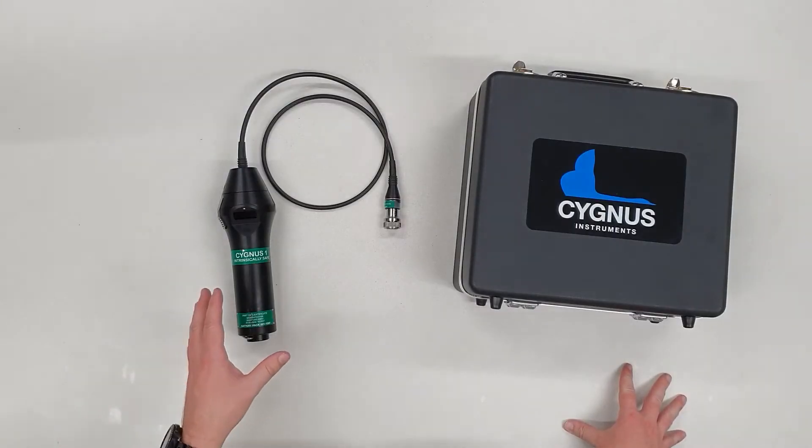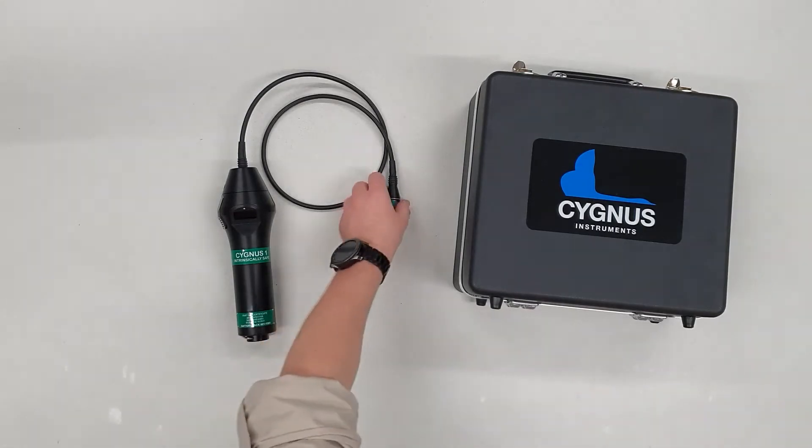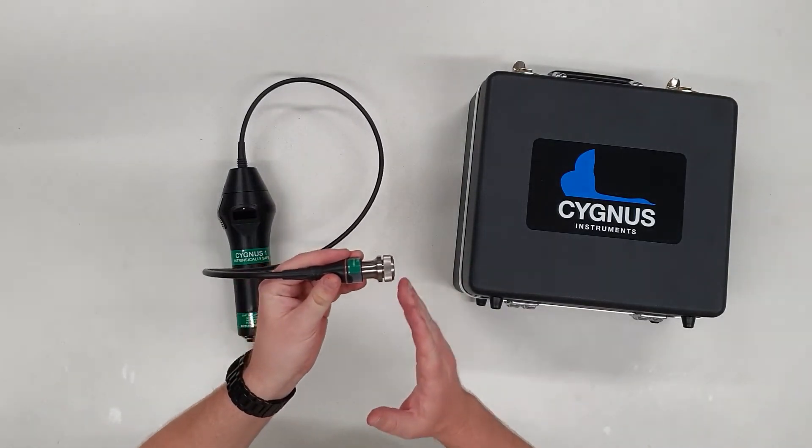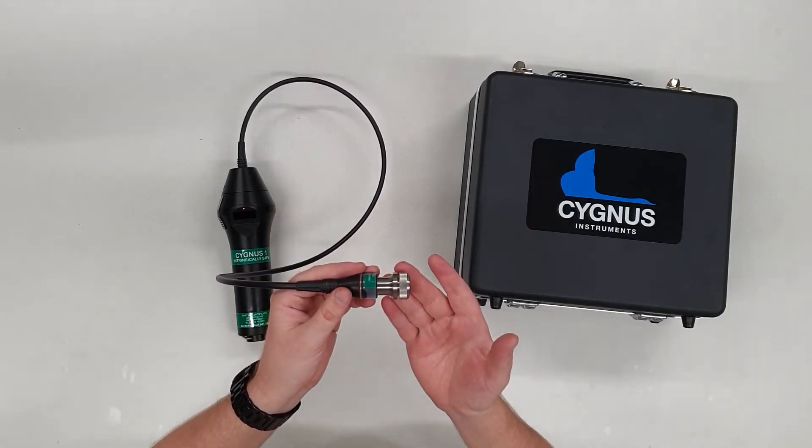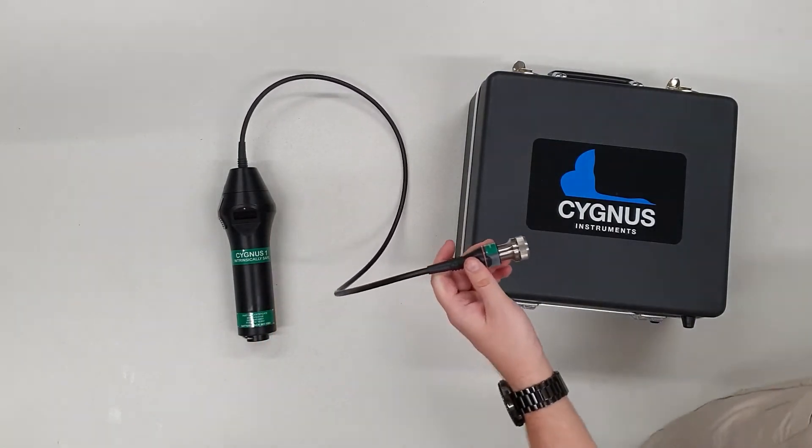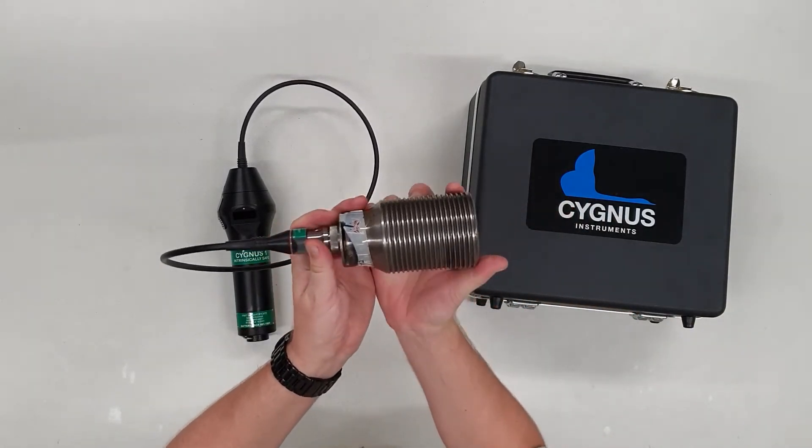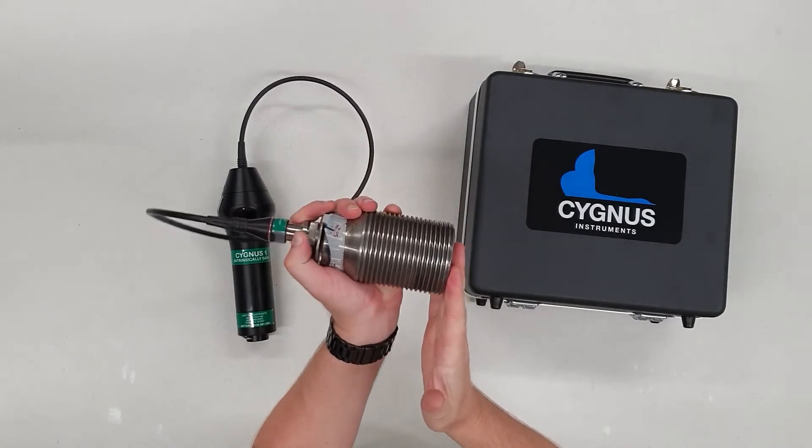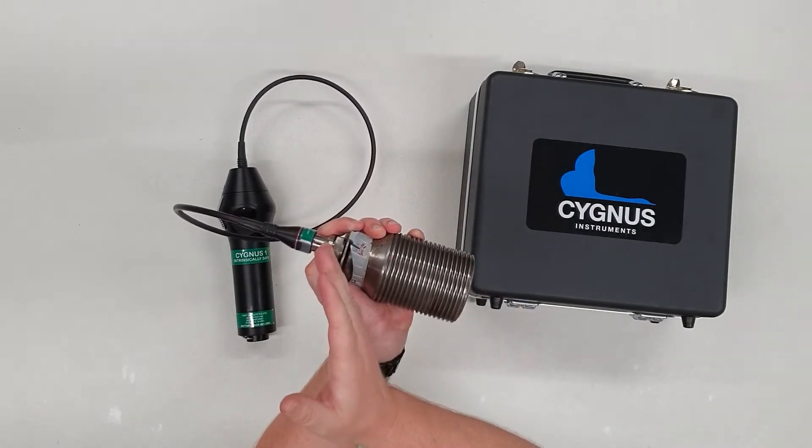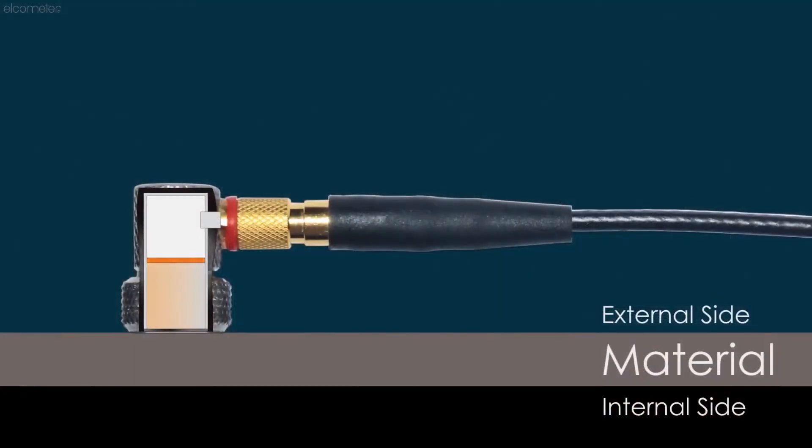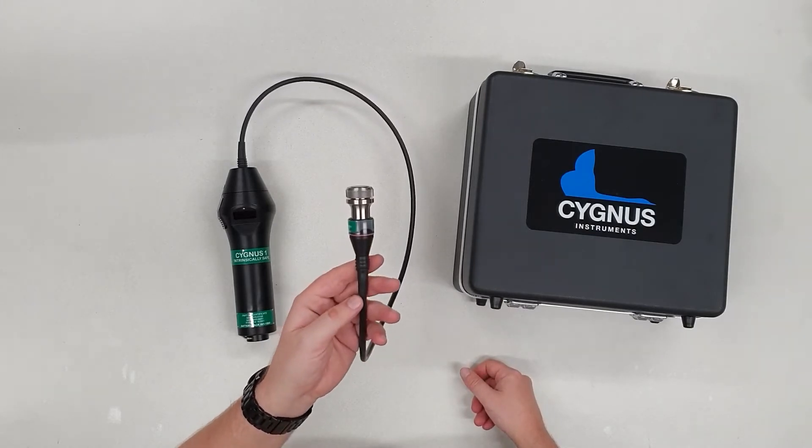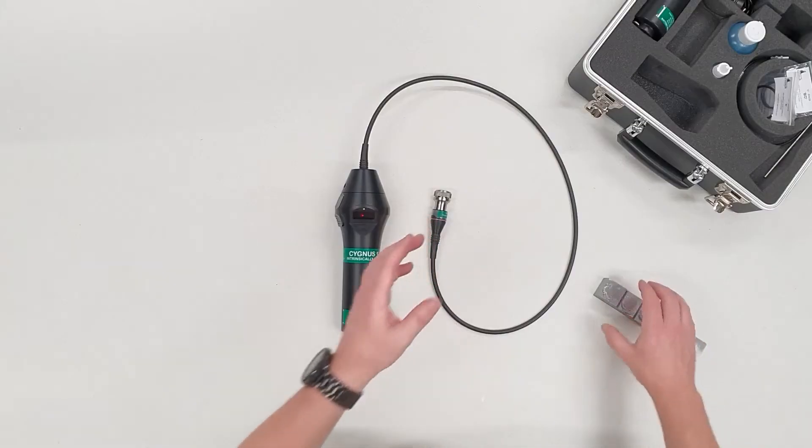The general principle for an ultrasonic thickness gauge is relatively simple. The probe will emit ultrasound from a crystal that vibrates at 2.25 megahertz. The sound will travel out of the probe into your part, travel through, hit the back wall and be reflected, then travel back where the echo is detected by the crystal again. The amount of time it takes to travel down and back is directly related to its thickness. If the gauge knows the ultrasonic velocity of the material, which in steel is around 5,930 meters per second, you can very accurately calculate the thickness.